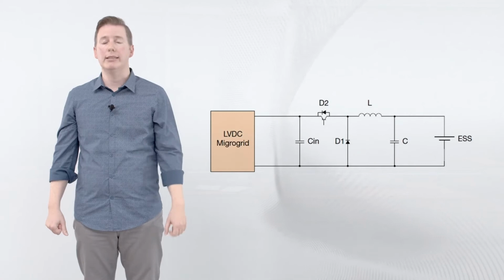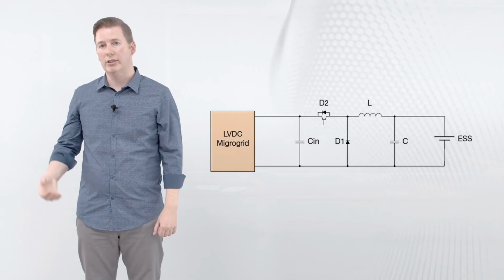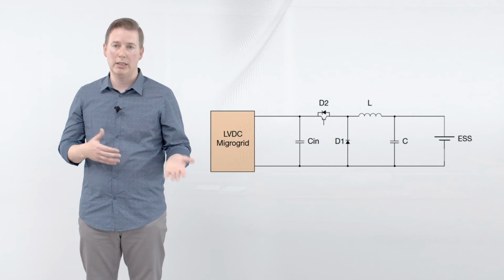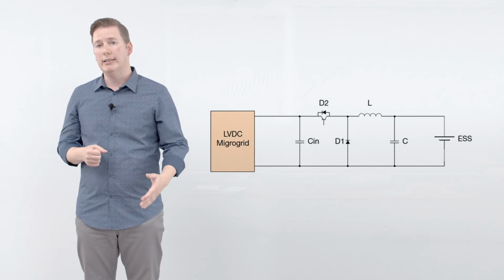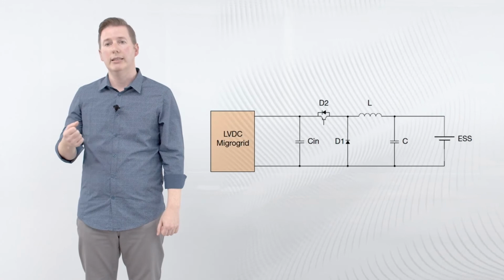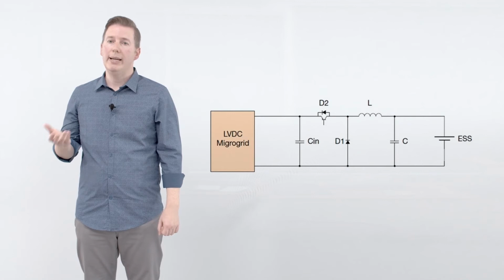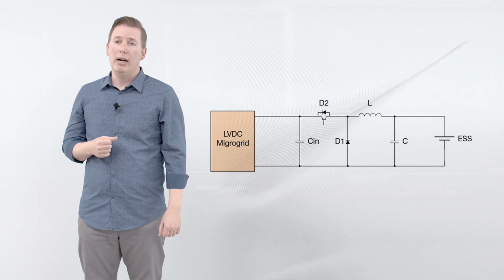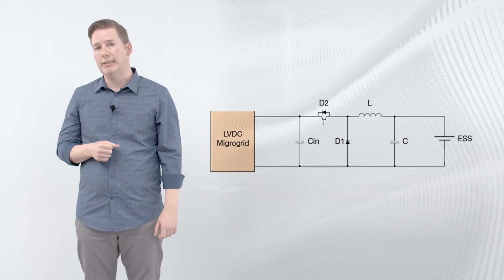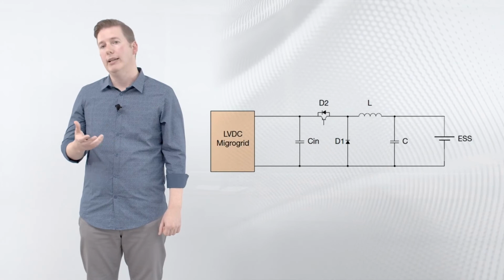Talking about the DC-DC converter, if the DC-DC converter is a so-called buck converter, in this case, as you can see, the output voltage, I mean the voltage on the load side, in this case the battery side, is lower than the input voltage, the voltage on the DC bus side. As you can see, if we have a short circuit in one of the locations that we have described before, the battery contribution to the fault will pass through the freewheeling diodes called D2 without any possibility for the IGBT to interrupt this current, even if we try to send the blocking signal by the control system.